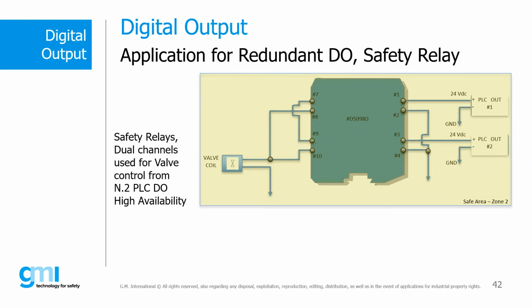A different application was one where we were asked to create a high security loop, where the final element was de-energized when only one of the two digital output cards sends a shutdown command. In this case, always using the same double channel SIL 3 relay, the desired safety function can be obtained by placing the relay output contacts in series. In this way, the safety level of the loop is increased to obtain the required function. This application makes us understand that sometimes it's possible to increase the safety or the availability of the process by combining low cost but very smart solutions, such as those proposed by GMI.